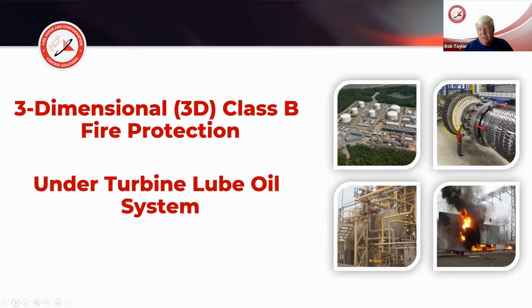and recognize that often these lubricating systems are providing lubrication to the turbine generator, bearings in both of those, as well as the pipings underneath them. So if there's a loss of piping containment, it can be a serious event, as well as generally the hydrogen, which is going to be available on the generator side as another hazard, and then the boiler feed pump. So all of these things together, you're dealing with stuff that is intended to lubricate some of the most expensive, longest lead time to replace equipment within any given facility. So you're dealing with equipment that is big bucks and makes big bucks. And with the fires, it doesn't take much. It can just absolutely wipe out the facility in just a second or so.